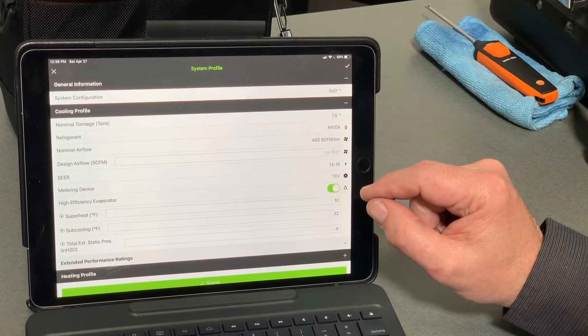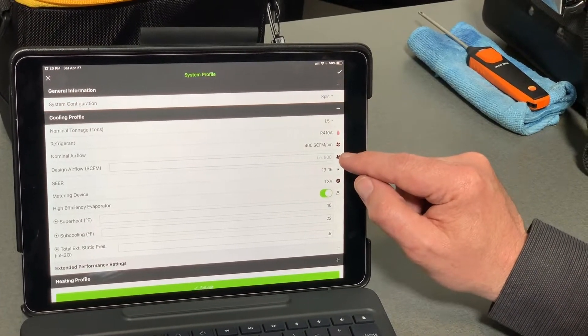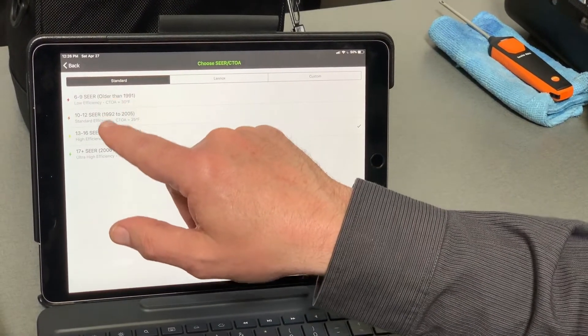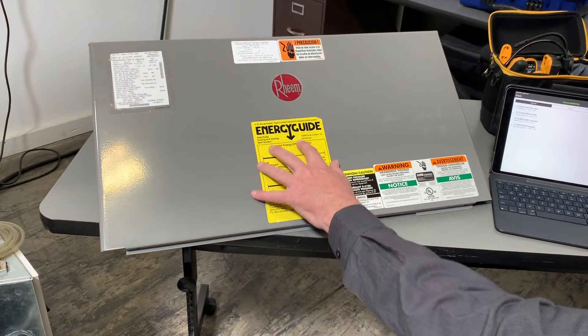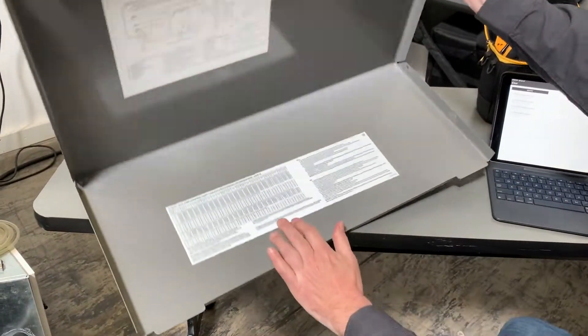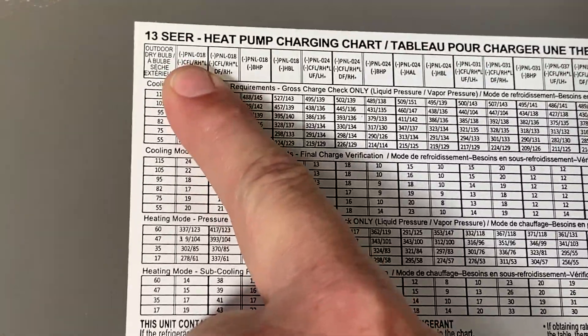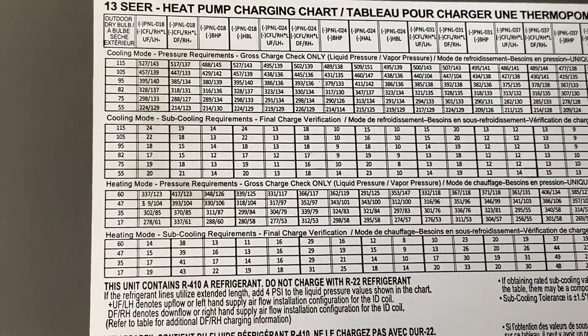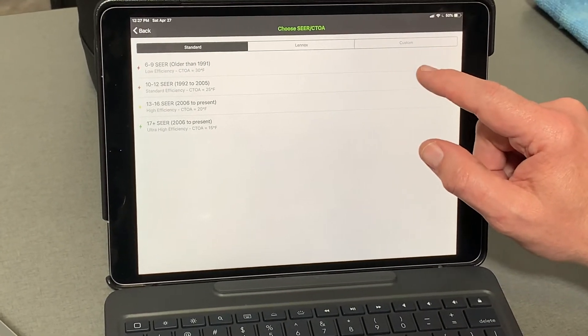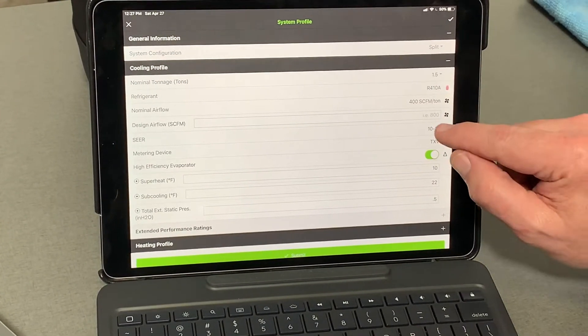If you have a design airflow — say you've done a heat loss calculation and have a different target sensible-latent split — you can enter the exact design airflow. Then we set the SEER rating; this unit is 13 to 16 SEER. You can find that on the system guide or look around the unit for indicators. In this case it's a 13 SEER unit. Older units like some really old ones might be 10 SEER, but just select the correct SEER rating and you're good to go.